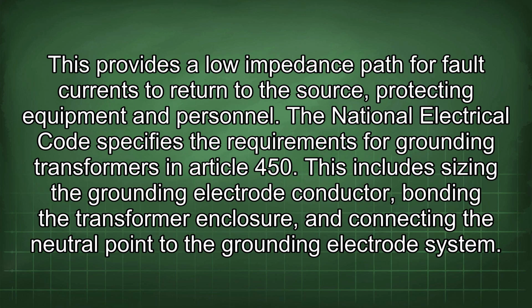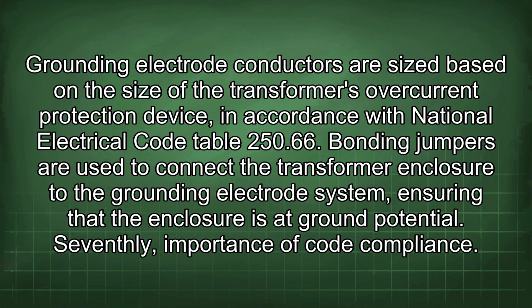The National Electrical Code specifies the requirements for grounding transformers in Article 450. This includes sizing the grounding electrode conductor, bonding the transformer enclosure, and connecting the neutral point to the grounding electrode system. Grounding electrode conductors are sized based on the size of the transformer's overcurrent protection device, in accordance with National Electrical Code Table 250.66. Bonding jumpers are used to connect the transformer enclosure to the grounding electrode system, ensuring that the enclosure is at ground potential.